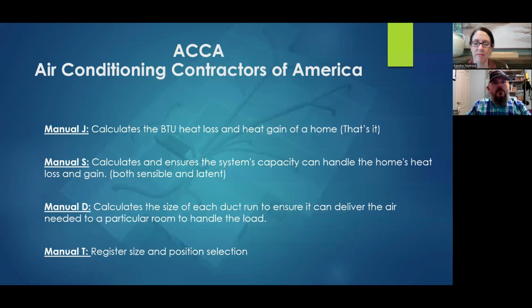Manual J, also called a J-load or load calc, calculates the BTU heat loss and heat gain of the home, and that's it - it tells me nothing about the AC system. Manual S calculates and ensures the system's capacity can handle the home's heat loss and heat gain, both sensible and latent, latent being the most important one.